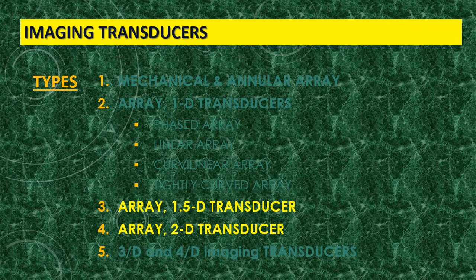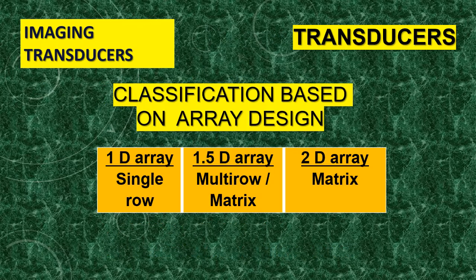In this lecture, we'll discuss the 1.5D and 2D transducers. To understand the difference between 1D, 1.5D, and 2D transducers, these numbers — 1, 1.5, or 2 — are talking about the arrangement of the active elements. It's not talking about the image. In imaging, we have 2D imaging and 3D imaging, but when you talk about the transducer design, that is a different matter.